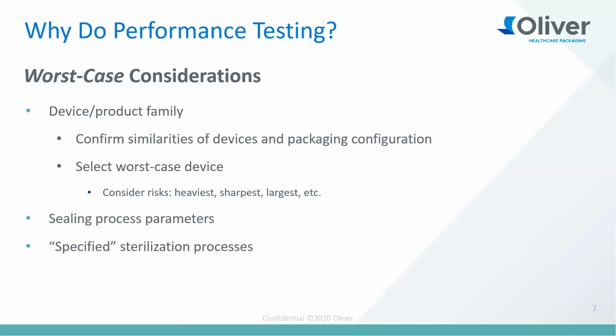And also, lastly, is sterilization. ISO 11607 indicates to use the specified sterilization processes. And this is another place where you want to go through risk. Do you want to go, for example, 2 times ethylene oxide sterilization? Do you want to go a little bit higher dose of a gamma cycle? That's all up to you. You want to look at the standard and go through your risk assessment to see what's appropriate for this testing.